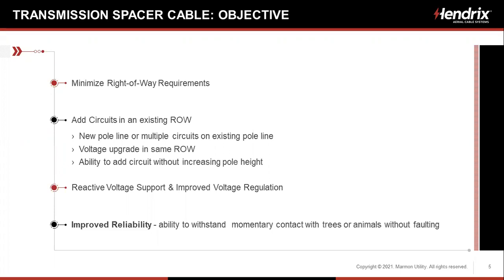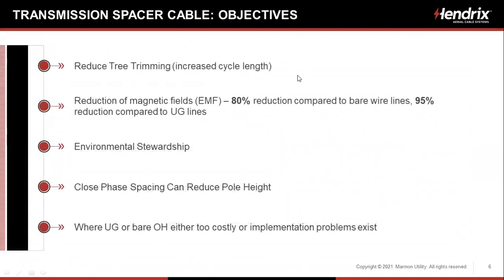We're going to have reactive voltage support and improved voltage regulation. We know that we've got, say, 15% less impedance, so we're going to have 15% voltage regulation. And improved reliability. We're going to have the ability to withstand momentary contact with trees and animals without a fault. Certainly going to reduce tree trimming or increase the cycle length.